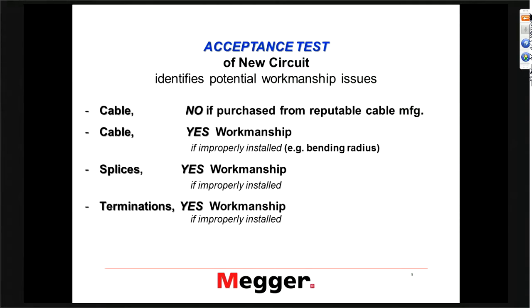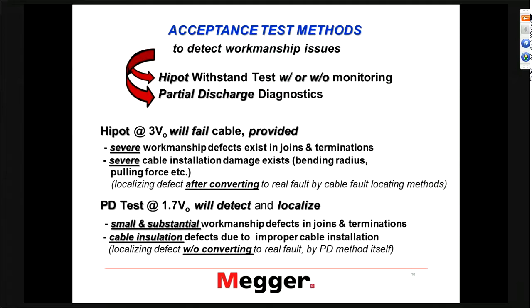What we're trying to do with the acceptance test, for the most part, is flush out workmanship issues. The acceptance test methods include a very common, well-known hipot withstand test either with or without monitoring, and we can do a partial discharge diagnostic test. The hipot test is a very common test — it has been done for many years, back to the days when we installed paper cables.